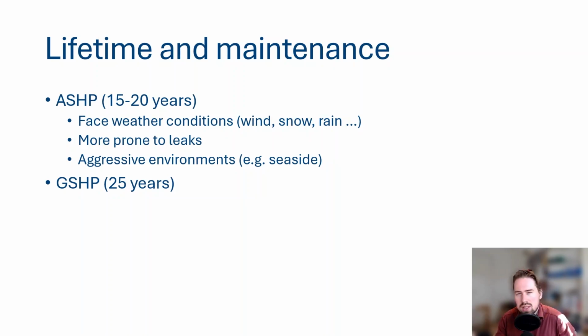Remember, if something goes wrong with the defrosting cycle and the heat exchanger, and there are some cracks in it, these air source heat pumps are more prone to leaks, which also means that their maintenance on average is a little bit higher. But also if you have, for example, aggressive environments, like at the seaside, the air contains some salt. And this salt damages the heat exchanger in the air source heat pump. So also there, the lifetime is sometimes even lower than these 15 years. So that's also something to take into account.